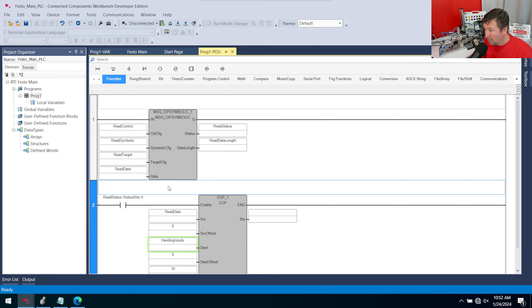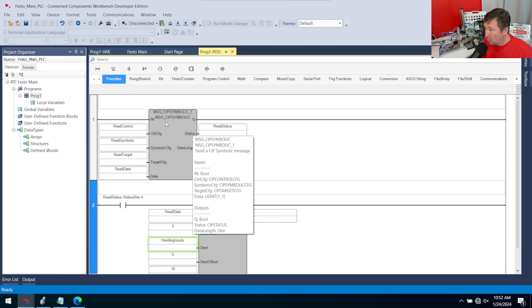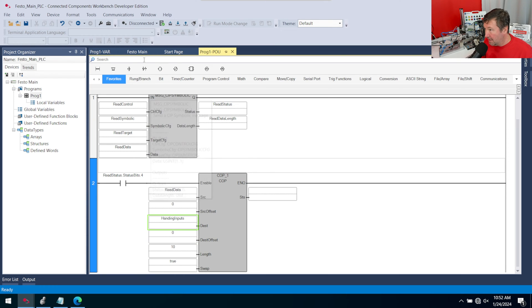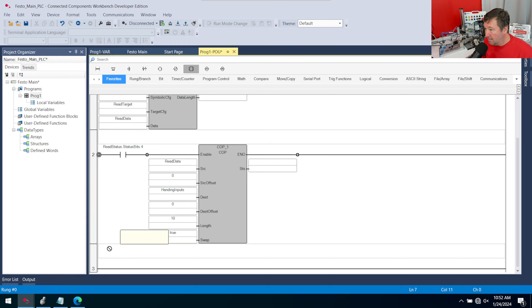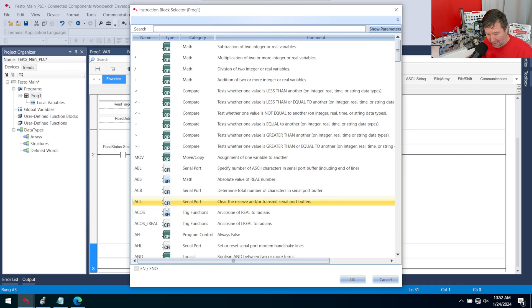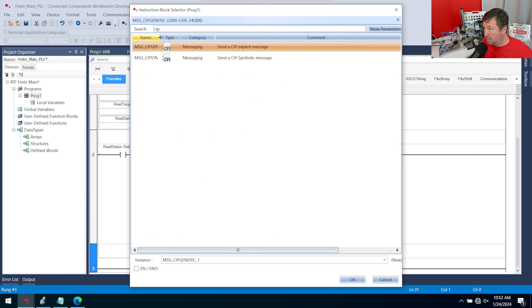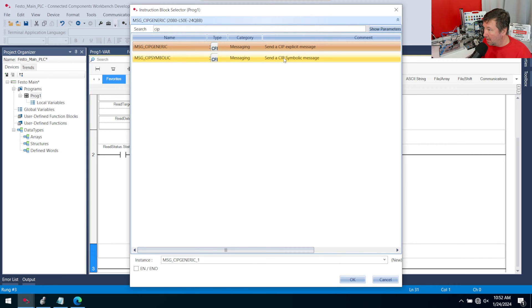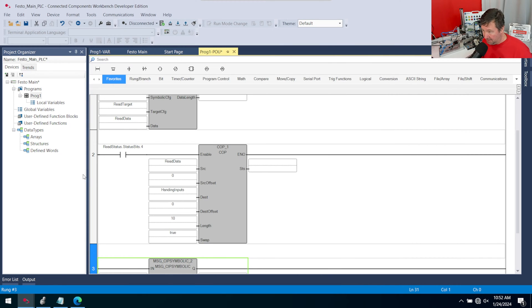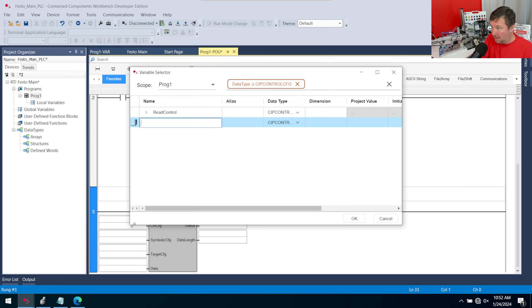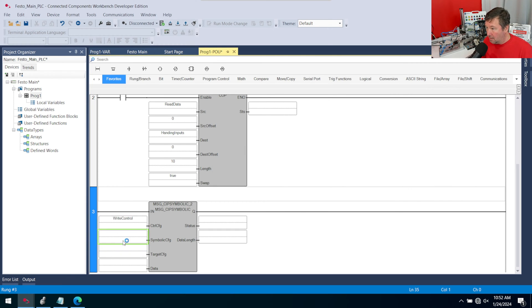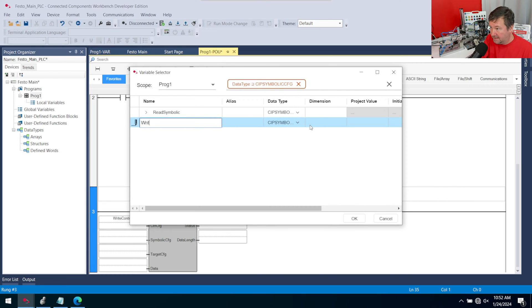These are the instructions we used in the previous video to read data. We're going to do almost the same thing — bring down a new rung and an instruction block, double-click on it, and type CIP. That brings up our two CIP message instructions. We are going to use the 'send a symbolic message.' Even though it says send, we can use that to write.